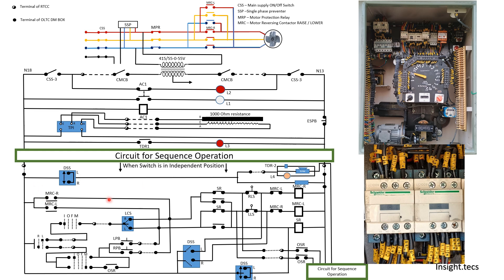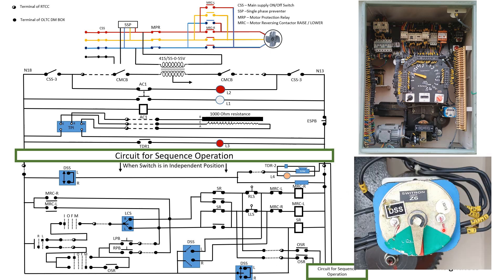Now we have discussed turning on the tap position change. How will the process be turned off? Say we started raising the tap position from 2 to 3 — it has raised, but when it reaches tap position number 3, how will it stop there? For that we have this switch called DSS. This is a very special provision and we will discuss the DSS switch in further detail in the next video. It is responsible for stopping the tap at a position once it has changed.